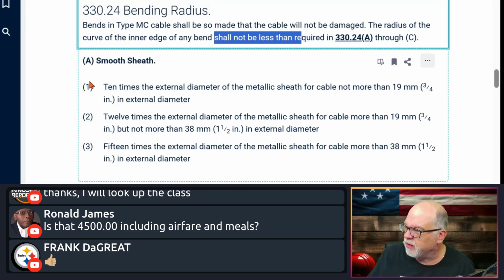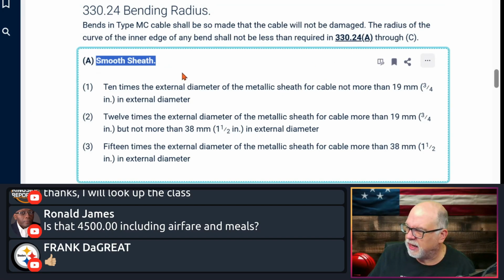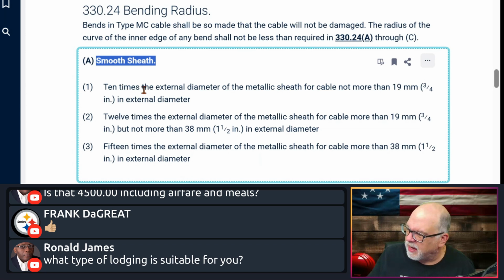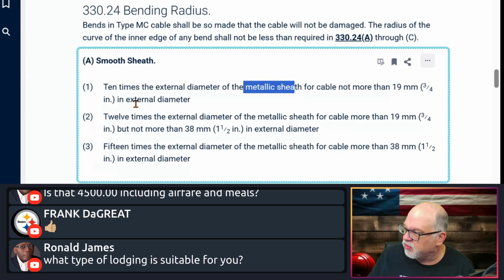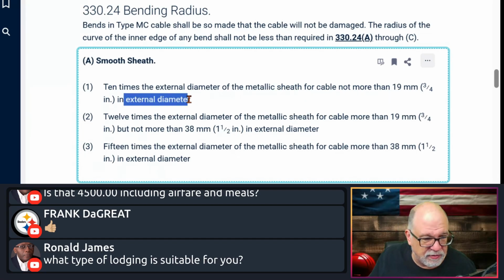All right. So smooth sheathed. That is extruded, not extracted, extruded. So it's 10 times the external diameter of the metallic sheathing for a cable if it is not more than 3/4 of an inch in external diameter. The manufacturer will give it to you.